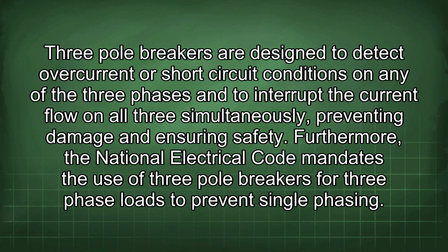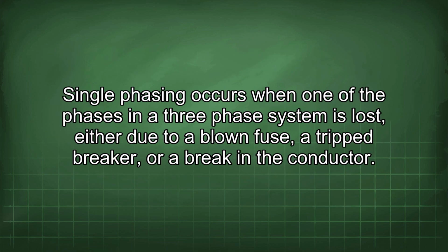3-pole breakers are designed to detect overcurrent or short-circuit conditions on any of the 3 phases and to interrupt the current flow on all 3 simultaneously, preventing damage and ensuring safety. Furthermore, the National Electrical Code mandates the use of 3-pole breakers for 3-phase loads to prevent single-phasing. Single-phasing occurs when one of the phases in a 3-phase system is lost, either due to a blown fuse, a tripped breaker, or a break in the conductor.